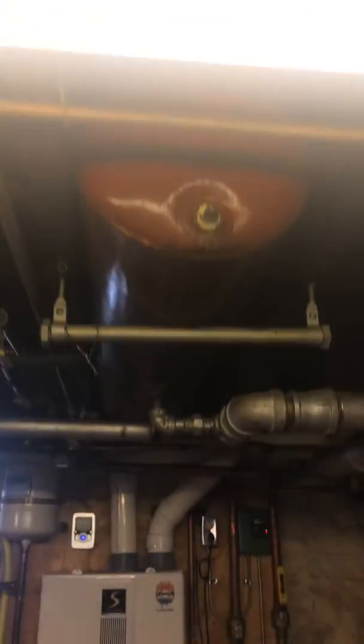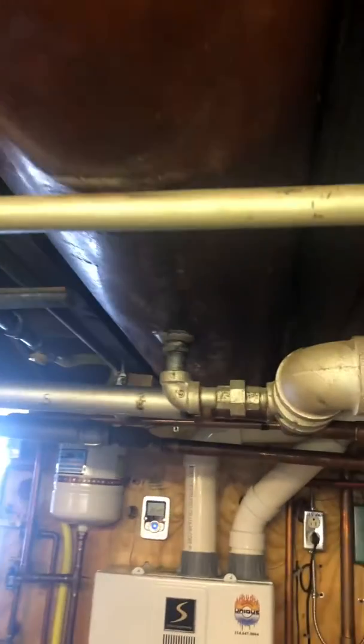The only things I can see that could be a potential issue: there's still a giant expansion tank up in the ceiling, still connected to all of the water lines. There have been some problems with the filter not being cleaned out properly on this system, and I think that could be causing some of the issues.